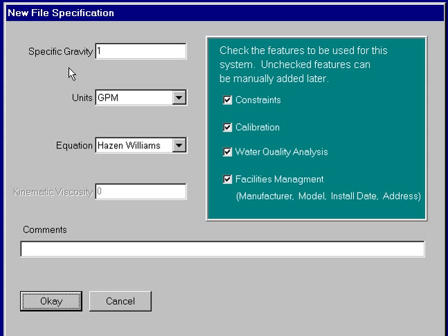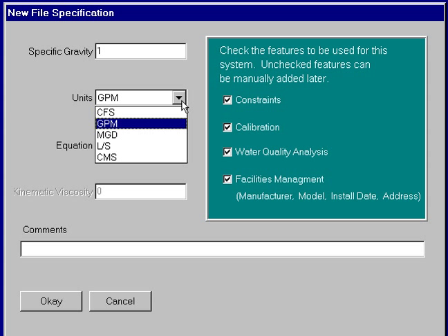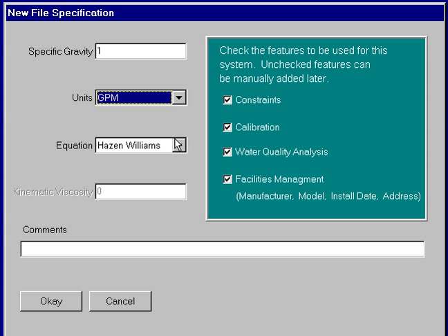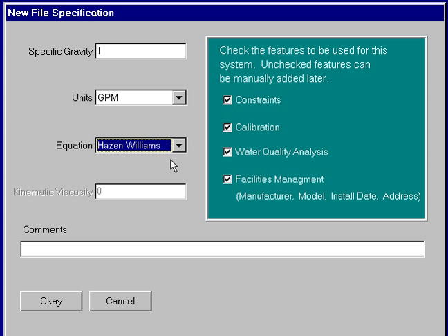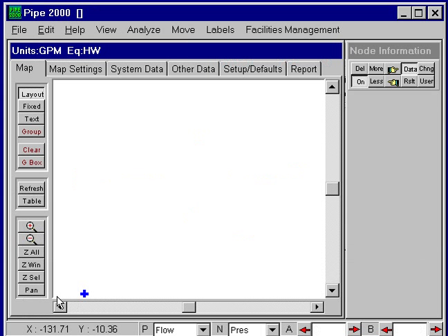The first screen that appears is a new file specification, which allows us to define the important data, the units, which will take gallons per minute, and the type of head loss equation we're going to use, and we'll use Hazen Williams. Some of these defaults for additional data won't really affect our problem, so we'll just accept the default that's shown and click OK.